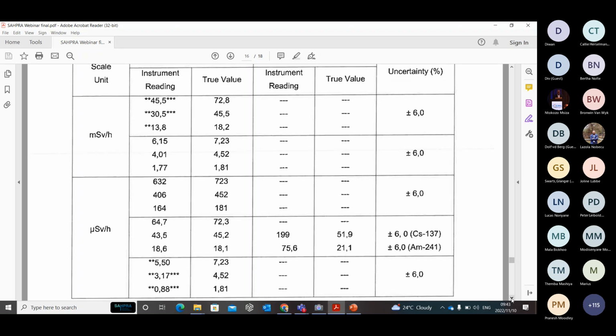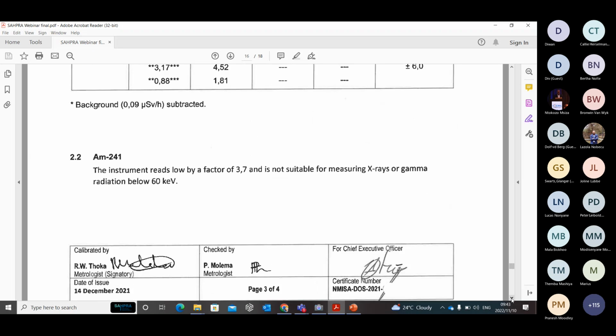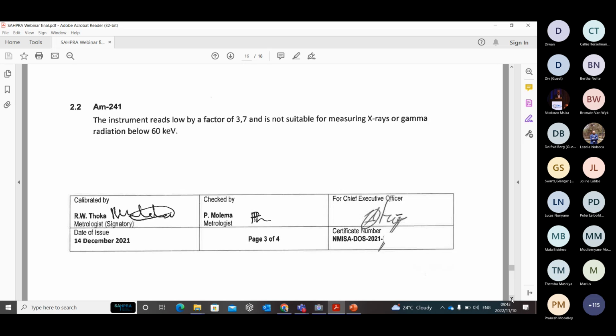Okay, Ditsola, we can then move further because I've run through the results. And there, you can see that we spoke of americium. When we calibrate in terms of americium, we're not really performing the whole range of measurements like we do with cesium. The only thing we're looking at is, can this instrument work at energies below 60 keV, or when you use the X-rays, depending on how you use your instrument.